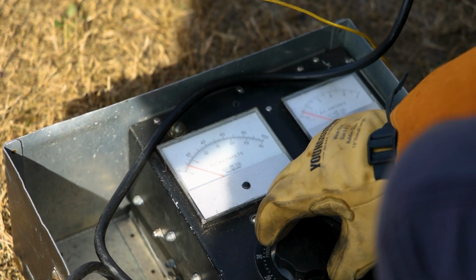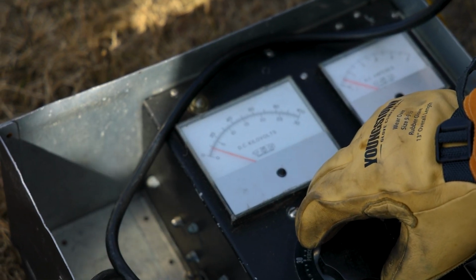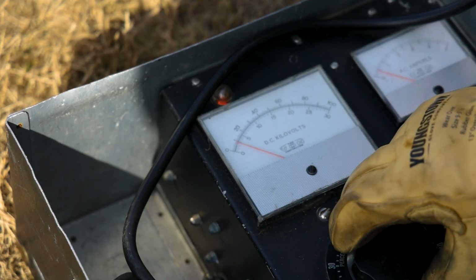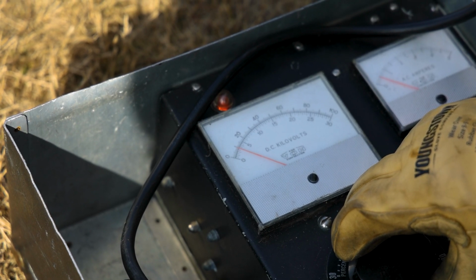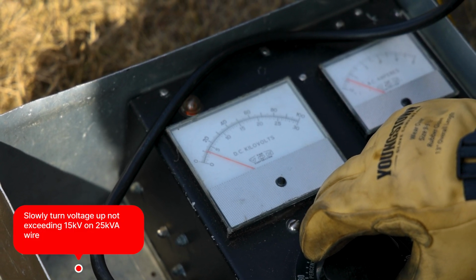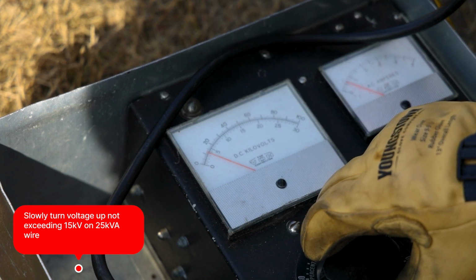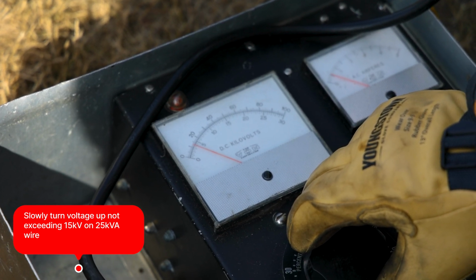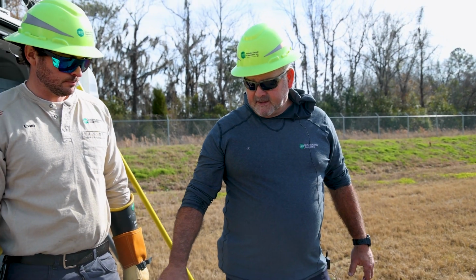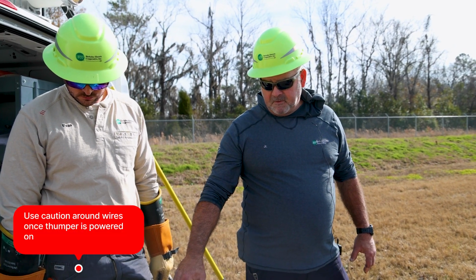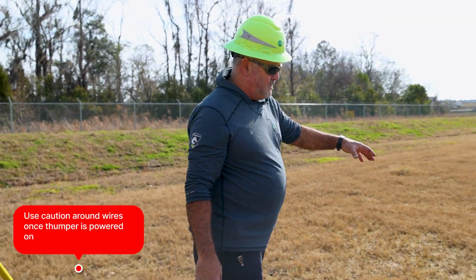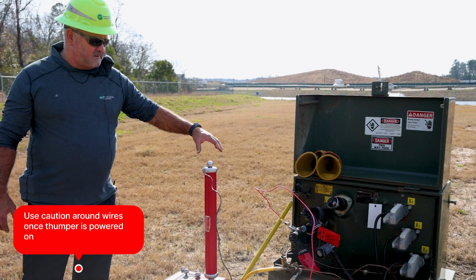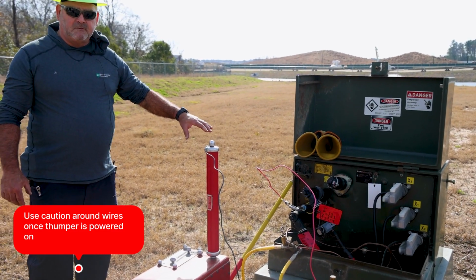and now he can start slowly turning his voltage up, watching his meter here, making sure that he doesn't exceed 15 kV on 25 kV wire. Now that he has the machine turned on to start thumping, you need to stay away from both of these boxes, especially these wires here, in case one of them was to pop loose.